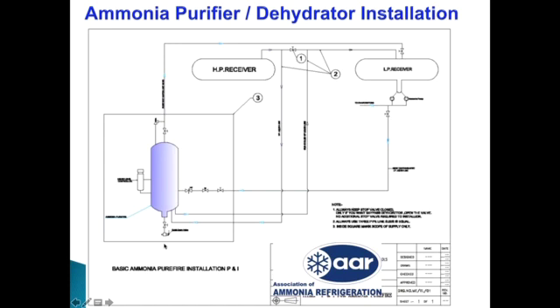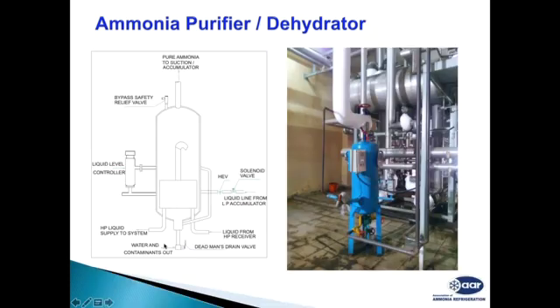Sir, I will try to answer the second question first. If you have a chiller system and you check your compressor system performance, if your suction pressure and discharge pressure are as per the design parameters and as per the ammonia pressure temperature chart, and you do not have any problem, you are able to maintain the corresponding pressures and temperatures, then you may not require it. But if you are not getting the performance from your chiller, your plant discharge pressure is higher than your design required condition, or your suction pressure is lower than your system requires, then you have to use these systems.